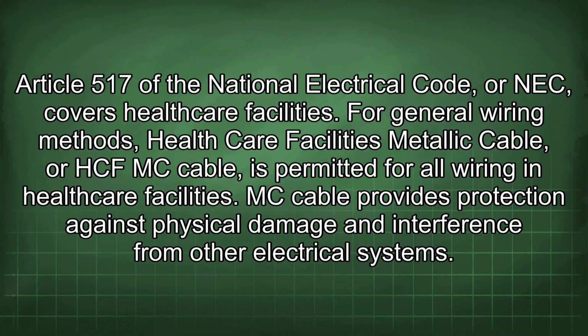Article 517 of the National Electrical Code, or NEC, covers healthcare facilities. For general wiring methods, healthcare facilities metallic cable, or HCF-MC cable, is permitted for all wiring in healthcare facilities. MC cable provides protection against physical damage and interference from other electrical systems.